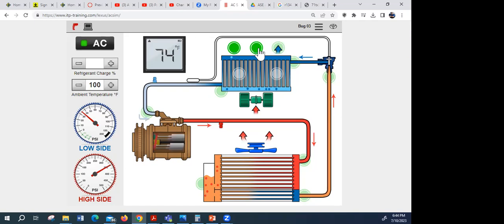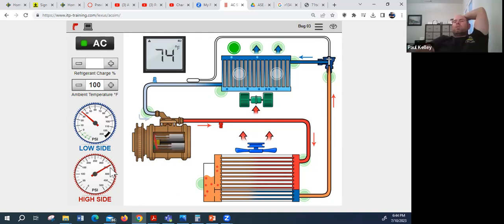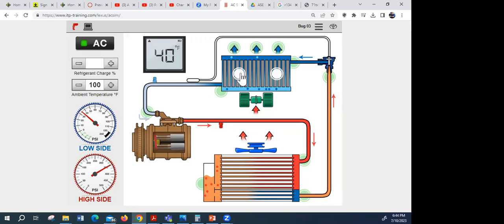The high side temperature gauge is very high. It is pretty high, huh? If we're getting 40, we're blowing 75 out the vents, 75 to 74. I'm seeing like 40 in the evaporator. What do you remember for the evaporator temperature on these previous questions, like on a good one? Like 33, like 30. Yeah, they shouldn't be at 40.